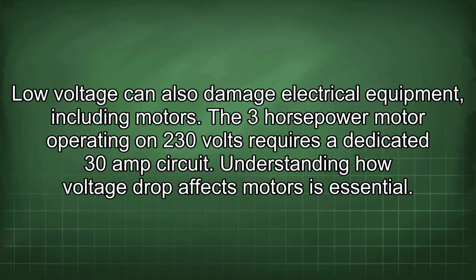Low voltage can also damage electrical equipment, including motors. The 3 horsepower motor operating on 230 volts requires a dedicated 30 amp circuit. Understanding how voltage drop affects motors is essential.